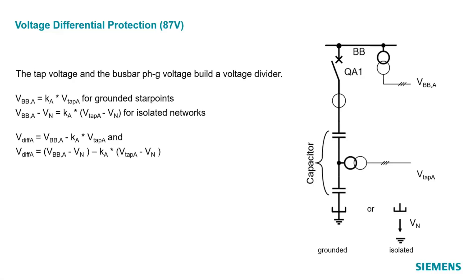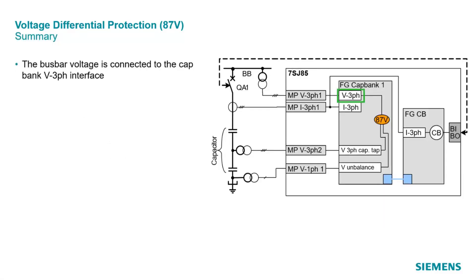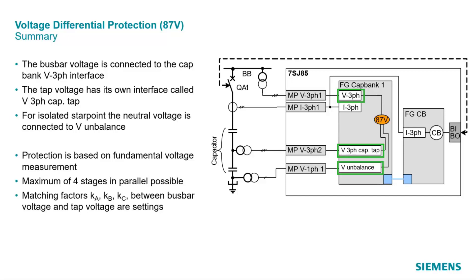For this, the function offers a compensation triggered by binary input or protocol. When triggered, the momentary voltage ratio between bus bar and tap voltage is measured for each phase and stored. The ratios then replace the setting values Ka in the formulae, now indicated by KCpa. The bus bar voltage is connected to the capacitor bank V three-phase interface. The tap voltage has its own interface called V three-phase capacitor tap. For an isolated star point, the neutral voltage is connected to V unbalance. The protection is based on fundamental voltage measurement. A maximum of four stages in parallel is possible. Matching factors between bus bar voltage and tap voltage are setting values, and the compensation of an operational differential voltage replaces the matching factor settings by the measured matching factors.